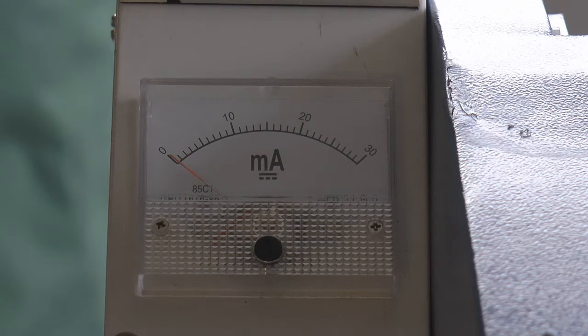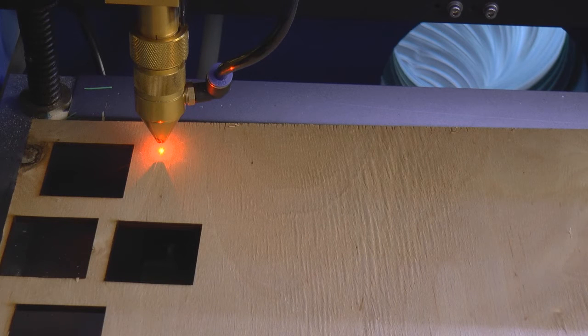Right, we'll now run it again at 75 percent and we are spot on 20 milliamps.